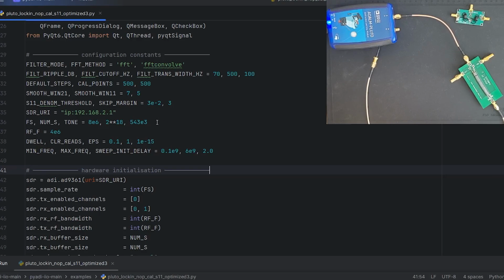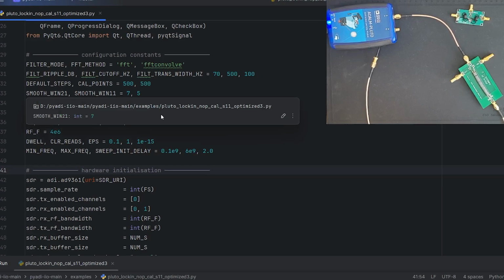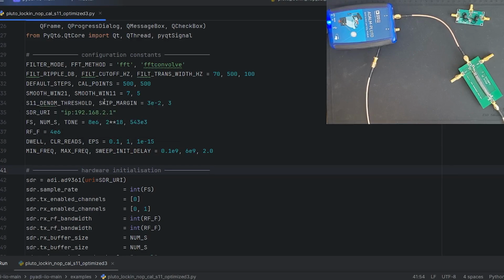One thing to note is that this is the case even for all the spectrum analyzers or the network analyzer. In order to reduce the noise and improve the resolution, either in the frequency or the amplitude measurement, which is basically lowering the noise floor, the main step is to increase the number of averaging. That means that we need to take more points for each read. If we increase the number of points, we have more points, so when we are doing the averaging or the filtering, we can apply a better filter. Also for the frequency axis, if we want to improve the frequency steps, we can increase the number of steps. But this means that for higher resolutions, we need to spend more time to get the measurement. And these definitely depend on the measurements we want to do.